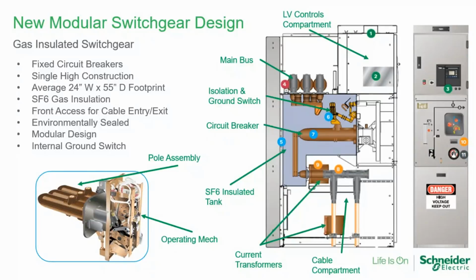One of the biggest benefits of this style of switchgear, and you really get this from the fixed circuit breaker style, is the environmentally sealed option. Basically meaning that some of the main operating components, the actual circuit breaker, the vacuum or SF6 operating bottles, things like internal disconnect switches and internal ground switches are all sealed away for the life of the switchgear inside an environmentally sealed tank. And this means that even though it's more difficult to do maintenance, it is required much less. So with GIS or SIS styles of switchgear, we're looking at 10-year maintenance cycles as opposed to yearly maintenance cycles on air insulated styles of switchgear.